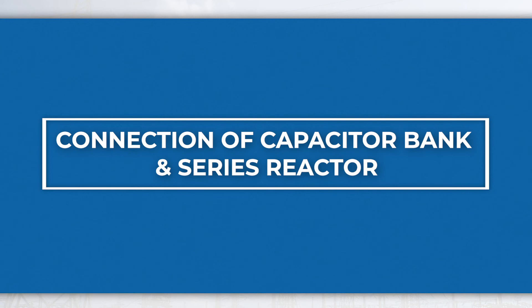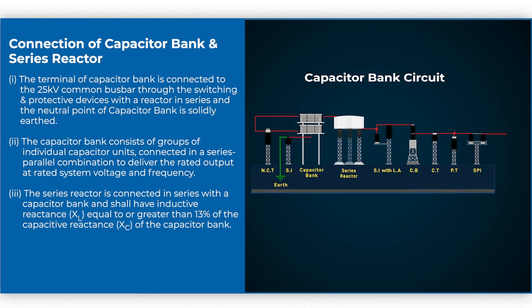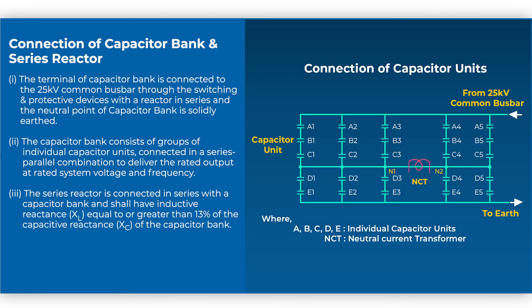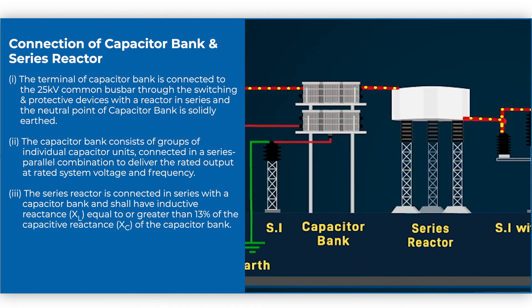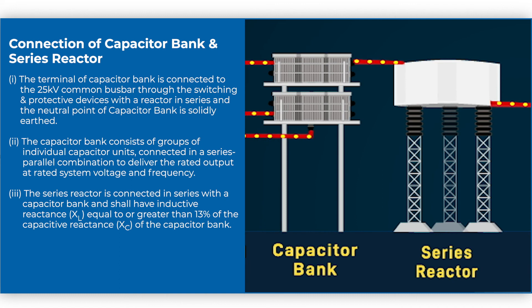The terminal of the capacitor bank is connected to the 25 kV common bus bar through switching and protective devices with a reactor in series, and the neutral point of the capacitor bank is solidly earthed. The capacitor bank consists of groups of individual capacitor units connected in a series-parallel combination to deliver the rated output at rated system voltage and frequency. The series reactor is connected in series with the capacitor bank and shall have inductive reactance equal to or greater than 13% of the capacitive reactance of the capacitor bank.